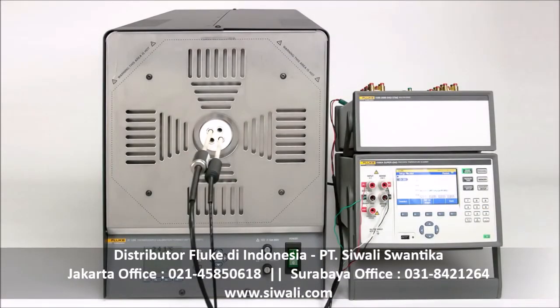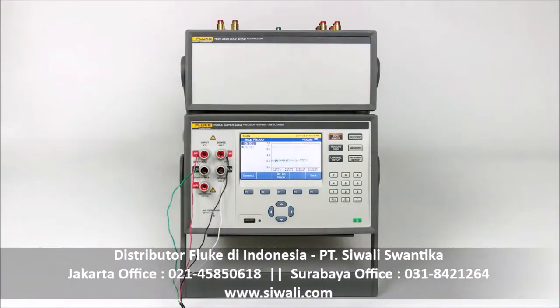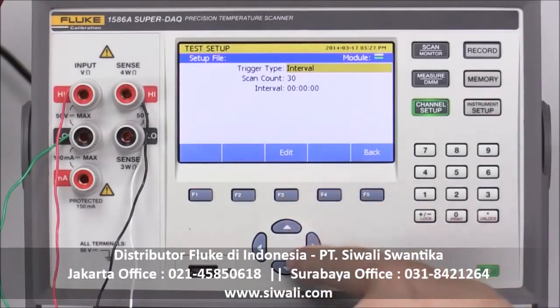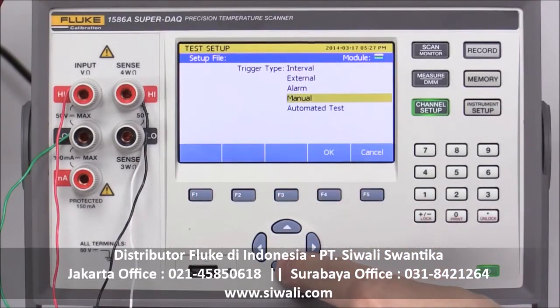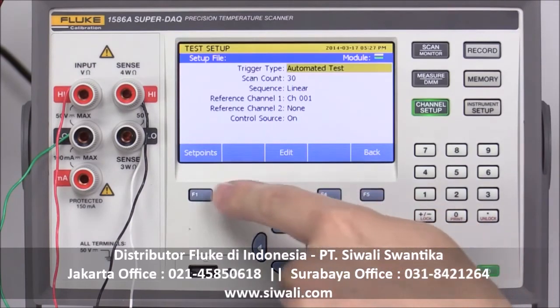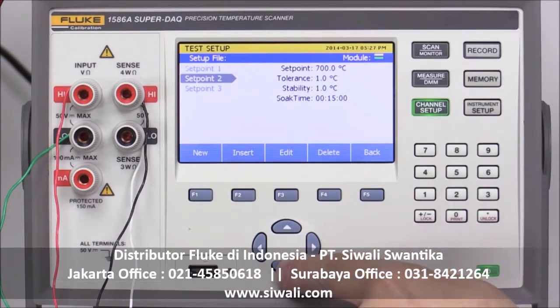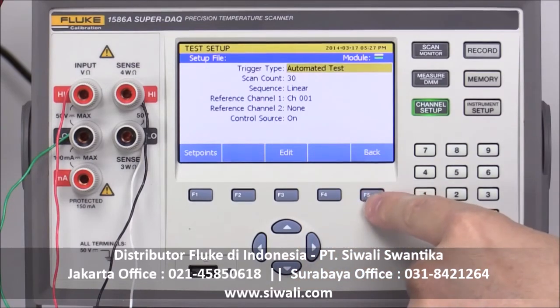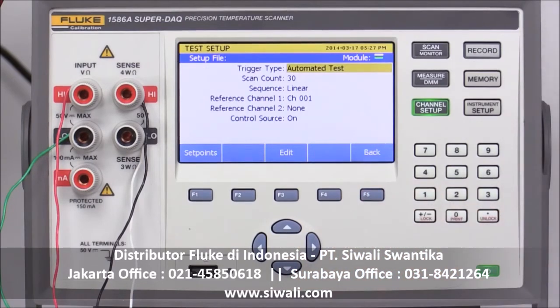Automation and data collection is further enhanced when used with the Fluke Calibration 1586A Super-DAQ. When the 1586A is connected through the RS-232 interface to the 9118A, the Super-DAQ will control and monitor the 9118A set point temperature, read up to 40 thermocouples, and automatically collect data. The Super-DAQ will then advance the 9118A to the remaining programmed set point temperatures, collecting data at each set point along the way. Once the test has been configured and started, the technician can walk away to work on other activities.